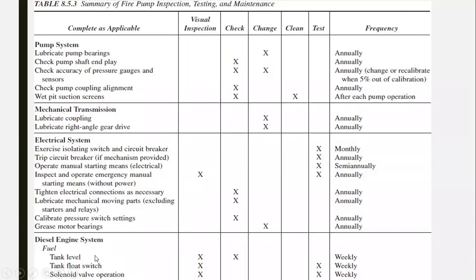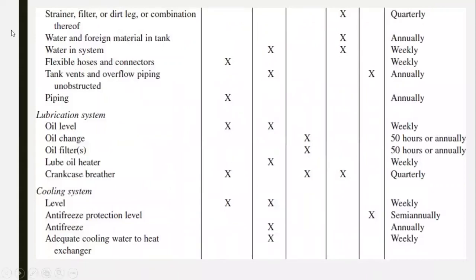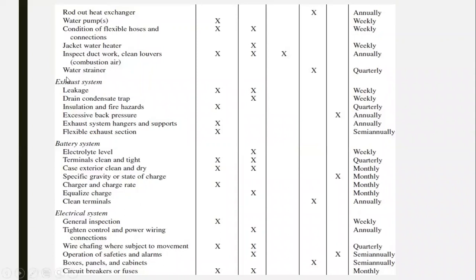Like the diesel fuel tank, it has to be visually inspected and checked weekly. Tank float switch: visual inspection weekly and testing weekly. Solenoid valve operation: inspect weekly and test weekly. Strainer filters, water and foreign material in the tank: inspect and check annually. Lubrication system: inspection weekly. Cooling systems. So it gives you all of the tests required. Exhaust system inspection, battery system, electrical system, and what will be required.